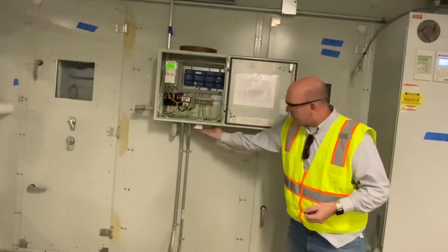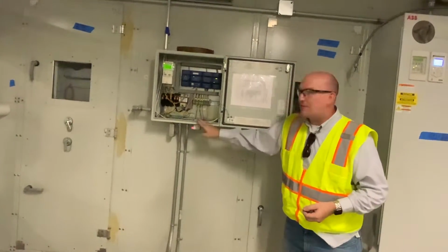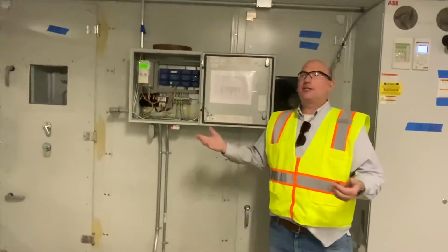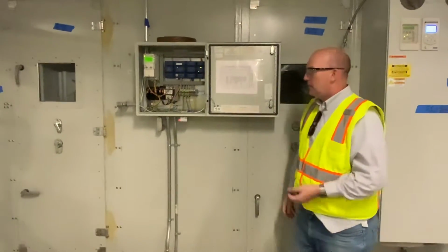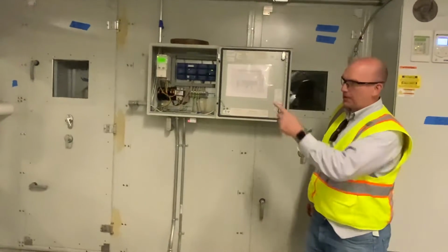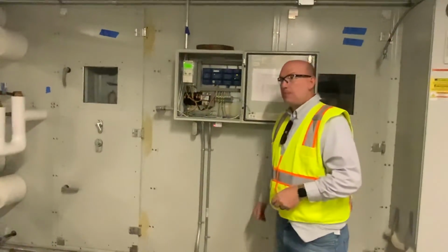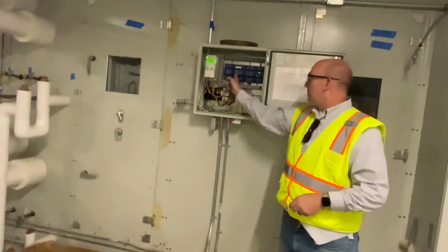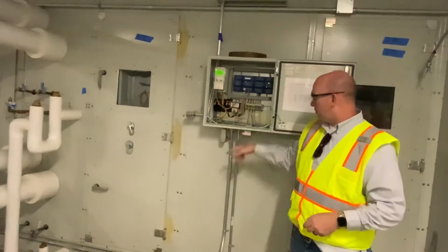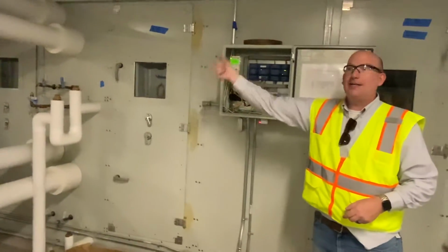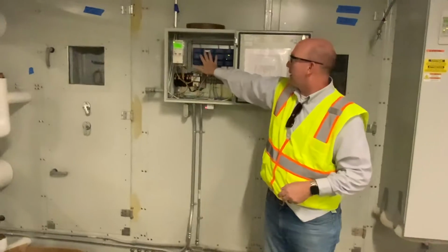So they're still using transponders. But, same situation here. We have a RIB relay. We do have a physical point to enable. All it does is just enable the wheels or disable them, and we're doing that right from our controller. So your set point is based off of that. You got it. Based off of this connection here, which basically runs over to that switch in there and ties into the BAS. So that's how we're getting our integration.